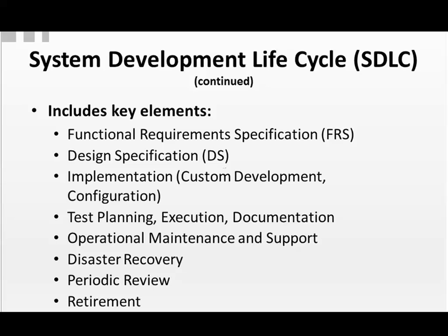You may be adding testing, different test scripts if you're making changes and including new functionality or turning functionality on. Your test planning should include the installation qualification, the IQ, the OQ, or operational qualification, and the PQ, or performance qualification, sometimes also called user acceptance testing. You want to make sure that you have a test protocol for each of these, that you execute them, and that you document everything accordingly, and create a summary report at the end. You should also have a validation summary report that details everything you were going to do in your validation plan to say that you did it as planned.